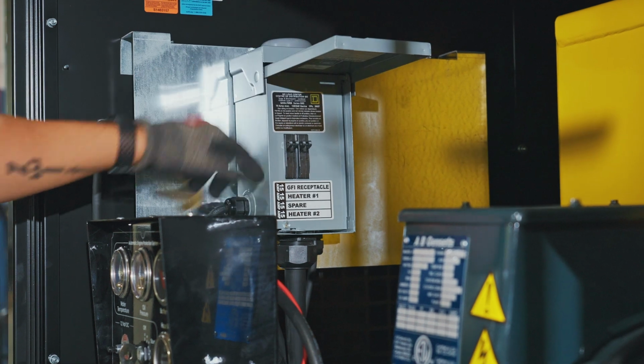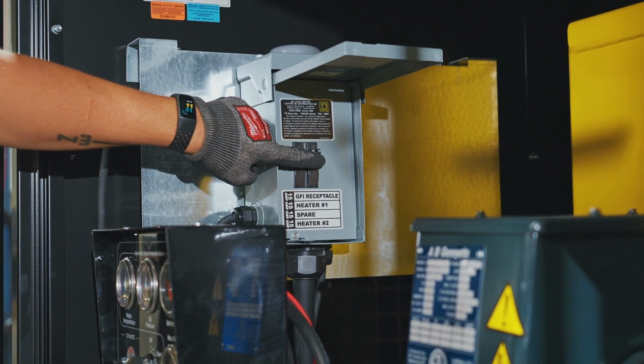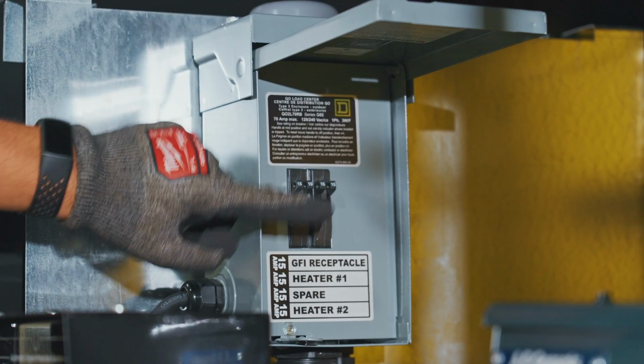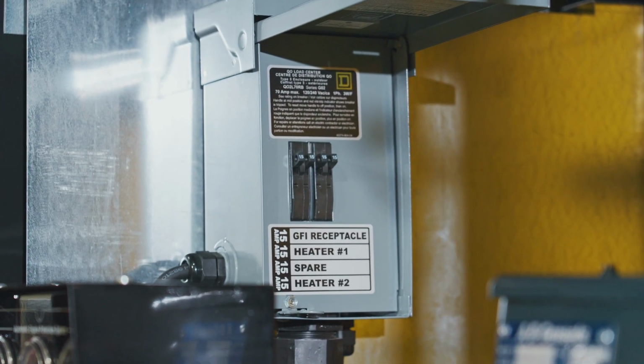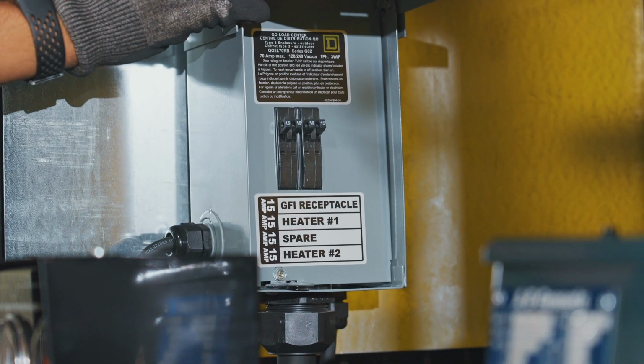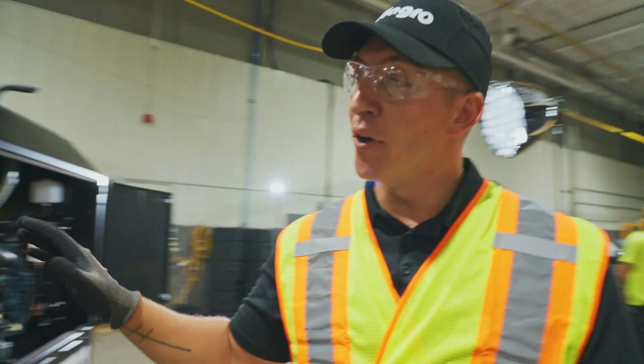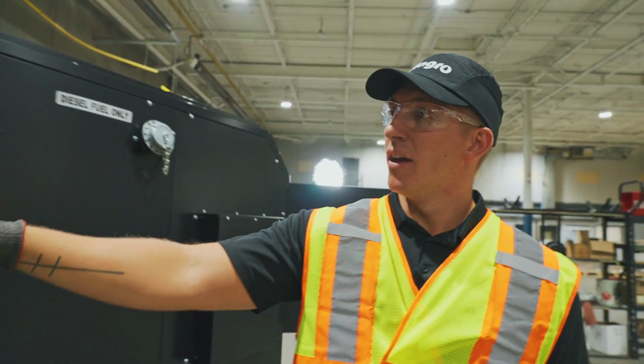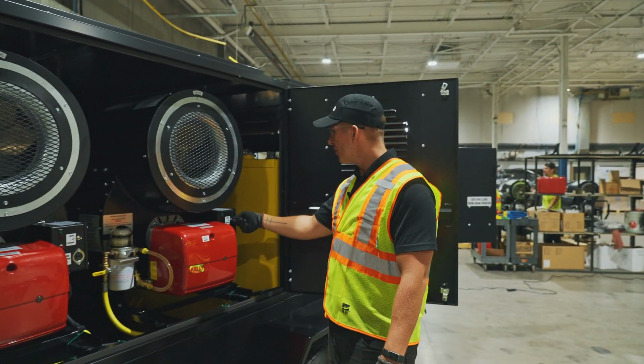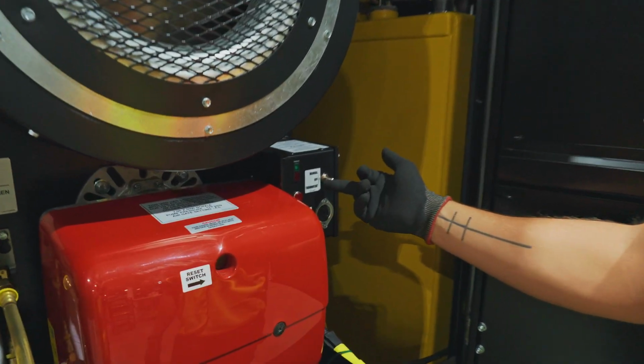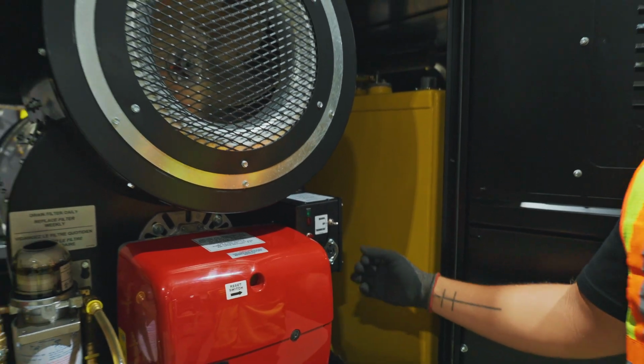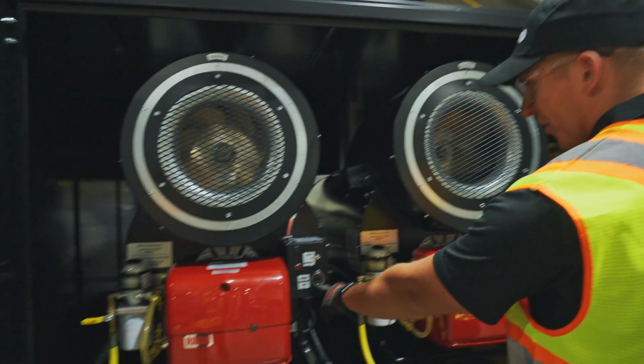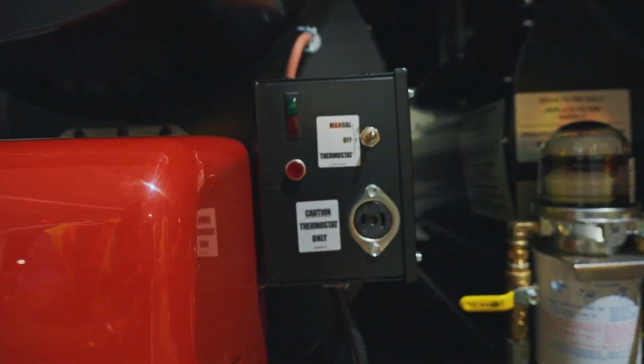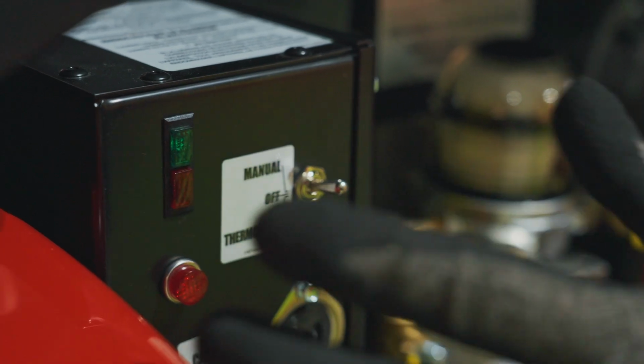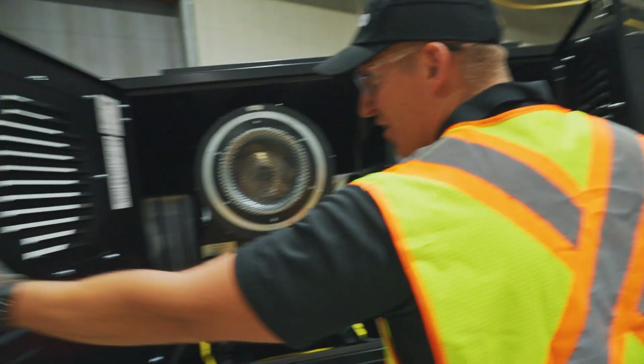So within this breaker box here, there's 2 breakers here on 15 amp. You want to make sure both of these are turned into the on position. Without these on, you're not going to get power to your GFI receptacle or your heaters in the back. So with your genset running at that point, you'll be able to come down here and switch your heat into manual mode. That'll start your heaters. If you're using a thermostat, you want to push this toggle switch down and have a thermostat hooked up to each individual heater, running at whatever temperature you choose there. So in turning these to manual mode, both heaters will turn on. At that point, you'll be all right to close your inlet doors.